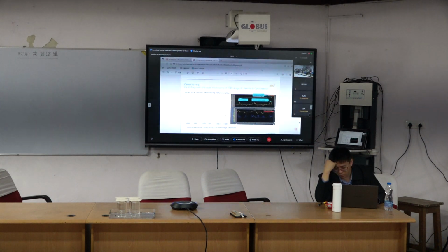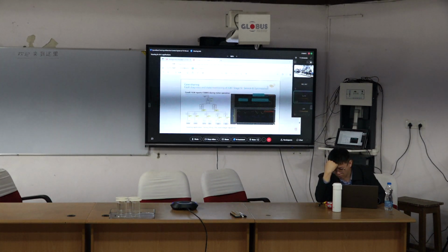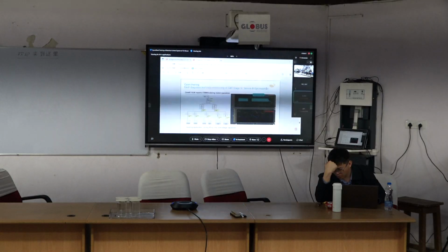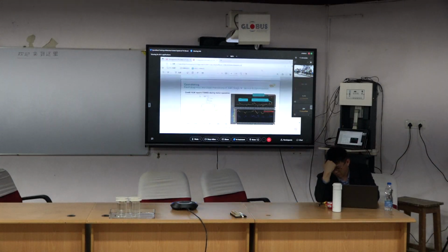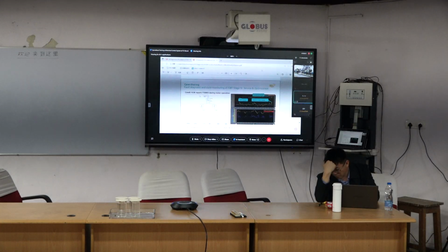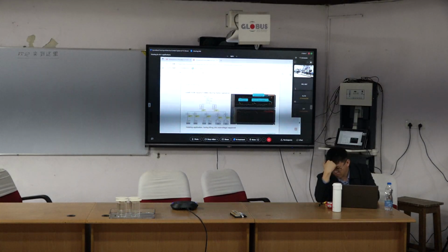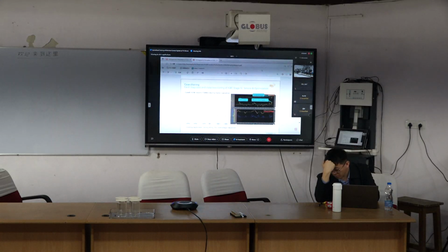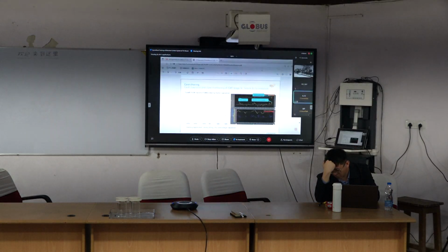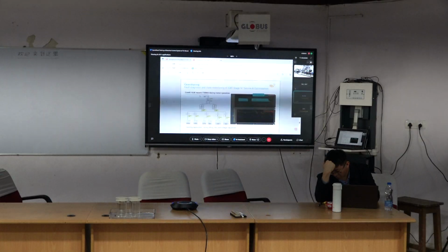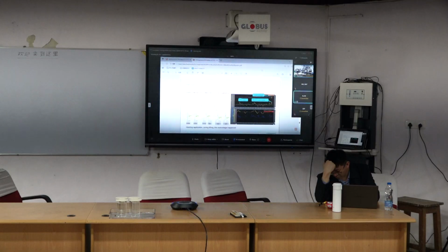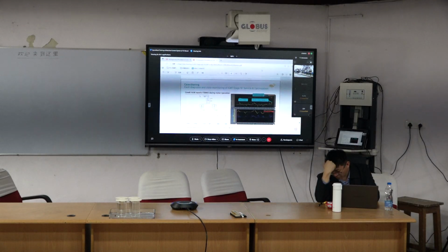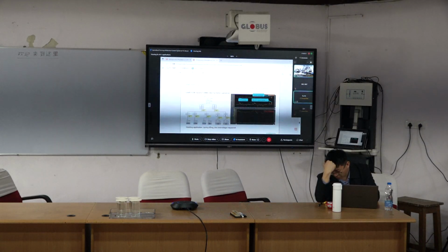The fourth step, service and optimization. Okay, this is the ALM, which reports overvoltage while the motor is operating. Let's review the working modes of the ALM. There are two working modes, motoring and generating mode. Normally, during the motoring mode, the DC link voltage will decrease.